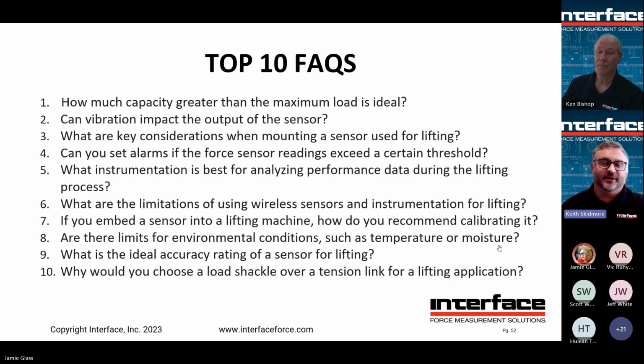What instrumentation is best for analyzing performance data during the lifting process? Well, typically you want instrumentation that allows logging of the data, and you might want a relatively higher sample rate than if you're just visually displaying the load. That's so you can look at it afterwards and see what happened. Again, if something drops, you may not even see it happening on a display, but if you were monitoring the load in real time with relatively fast data collection, you might see these spikes.